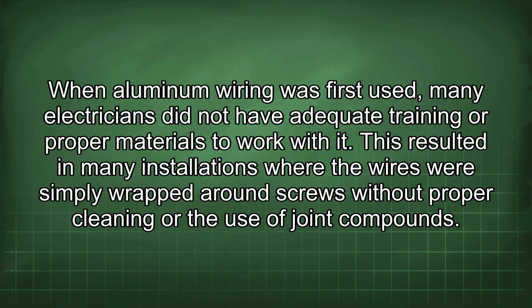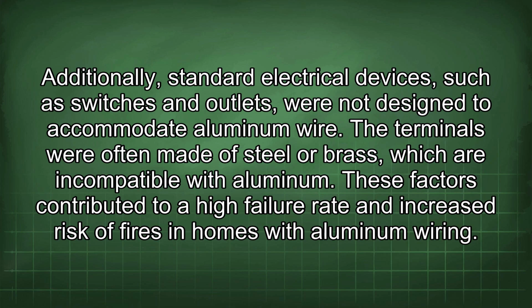When aluminum wiring was first used, many electricians did not have adequate training or proper materials to work with it. This resulted in many installations where the wires were simply wrapped around screws without proper cleaning or the use of joint compounds. Additionally, standard electrical devices such as switches and outlets were not designed to accommodate aluminum wire. The terminals were often made of steel or brass, which are incompatible with aluminum. These factors contributed to a high failure rate and increased risk of fires in homes with aluminum wiring.